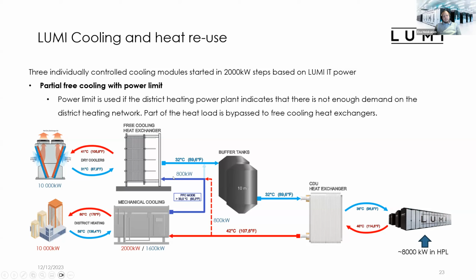And then they are still running in series, so all of the flow goes through the free cooling heat exchanger. And in this case, when we are taking out 1/3 of the cooling capacity of the heat pumps, we are also taking out 1/3 of capacity from the district heating. So this is the mechanism how we adjust the district heating based on the demand on the district heating network.